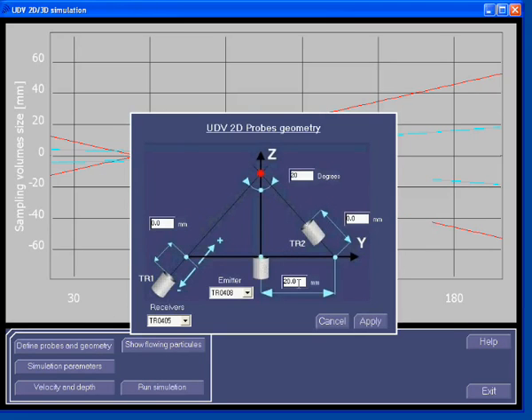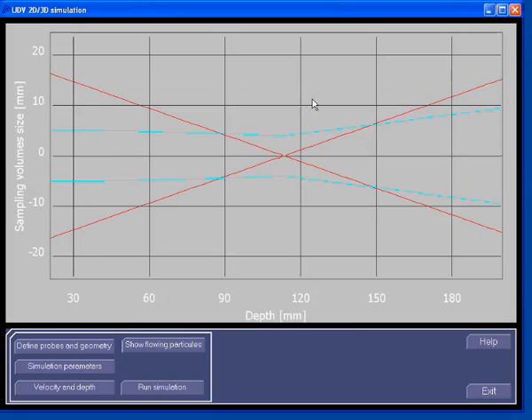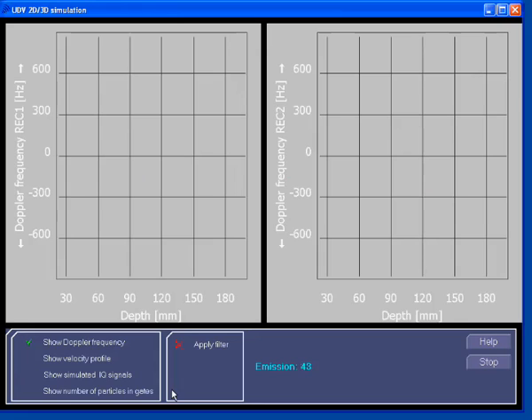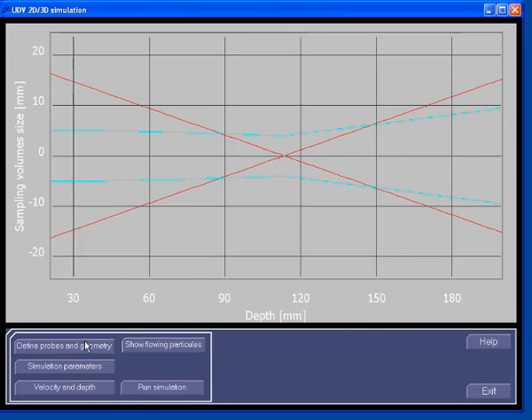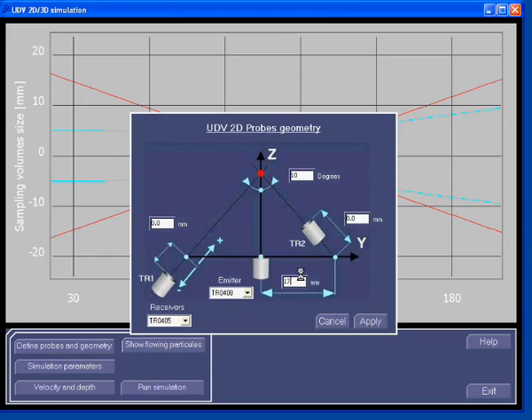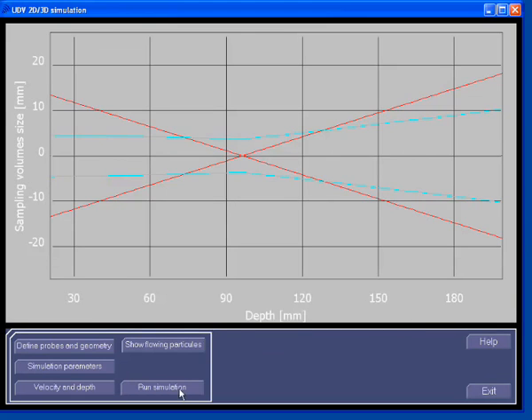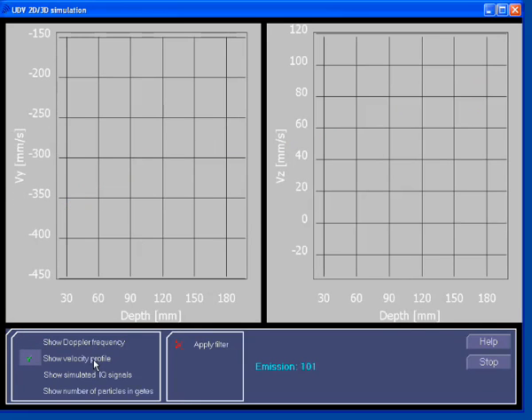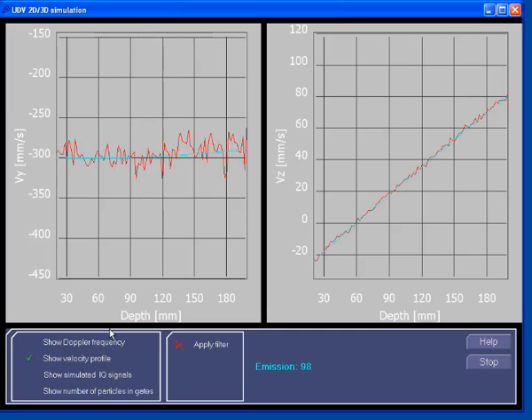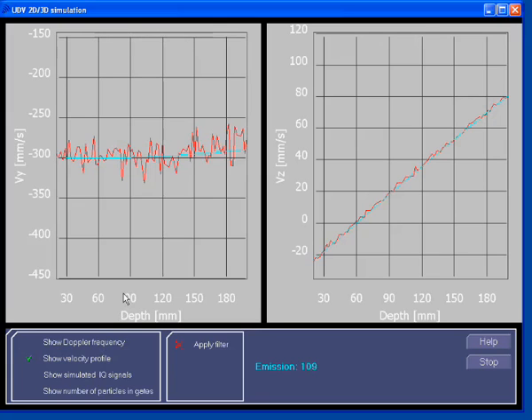Let's move the probe a little bit. We can change the distance or change the angle — let's change the angle to 10 degrees. As you may realize now, the beam crosses at a much better position. Looking at the result of this change, the velocities are now correctly measured at higher depths. But at lower depths, we have a small region where the measured values are not correct. Let's change again the position of the probe and reduce the distance between the probes to 17 millimeters. Now the Doppler frequencies are correctly measured, and we have a close match between the measured value and the theoretical values on the velocity profile.